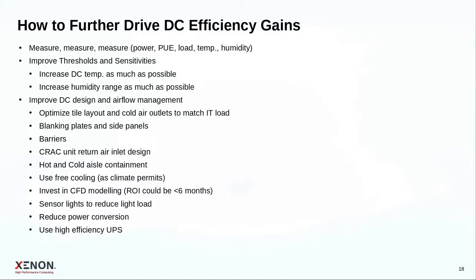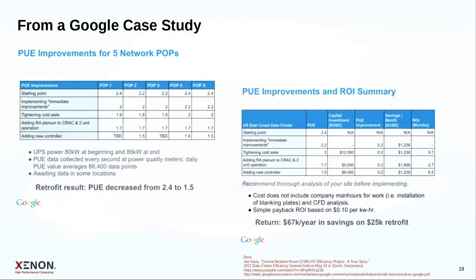It's really a retrofit of an existing system from Google a few years ago, where they looked at network points of presence. They started out with PUEs on the order of 2.2 and 2.4 in five different network POPs, which is pretty inefficient - for essentially 100 kilowatts of power, they needed 220 kilowatts to keep the system cooled and running.